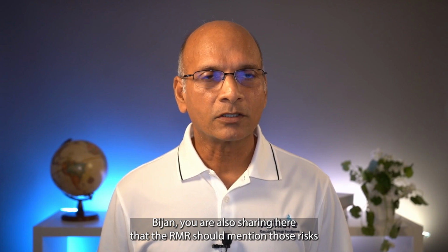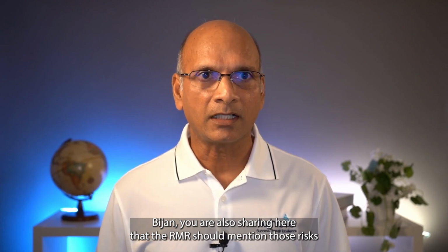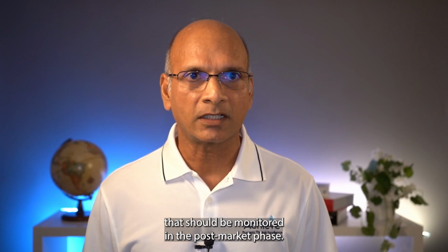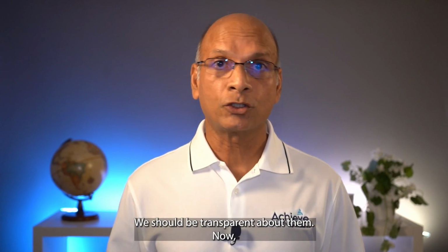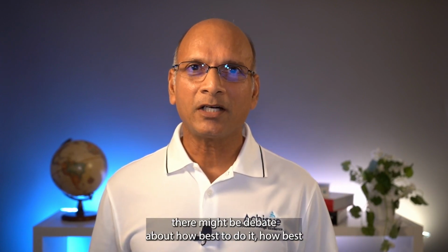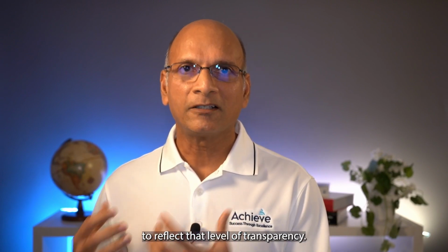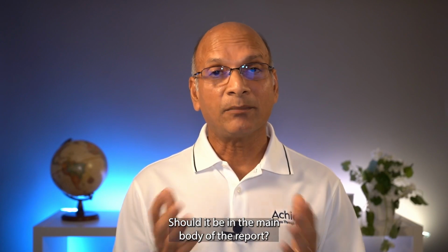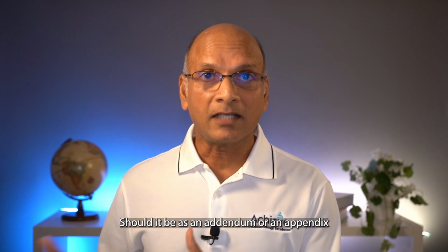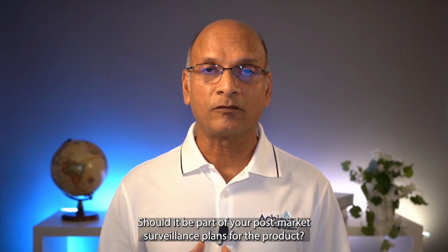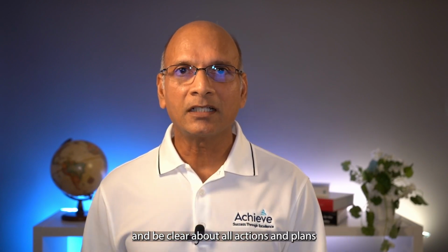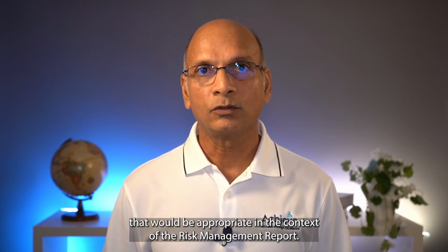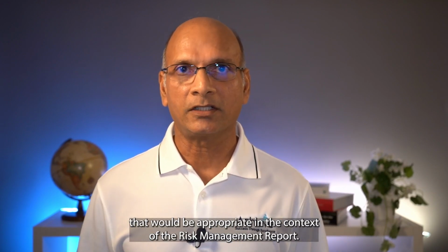Bijan, you are also sharing here that the RMR should mention those risks that should be monitored in the post-market phase. This supports transparency. Great. So that was a good response to the question. We should be transparent about them. Now, there might be debate about how best to do it, how best to reflect that level of transparency. Should it be in the main body of the report? Should it be as an addendum or an appendix? Should it be part of your post-market surveillance plans for the product? How best to do it? But the key point here is that we should be transparent and clear about our actions and plans that could be appropriate in the context of the risk management report.